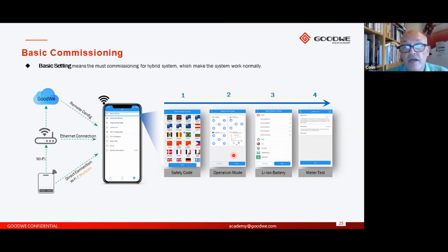Having done that, we can now select Next, which takes you onto the screen where you'd select the batteries that you selected to be used with this system. So you just go through the drop-down menus and select the appropriate configuration, and then the final step would be to press Next to get you onto this final screen called Meter Test. Now, Meter Test enables you to ensure that you have got the CTs connected on the incomer the right way round, because there is an orientation required with the CTs, and providing that you have got the equipment all configured and all set up correctly, this does enable you to check that the CT is correct.